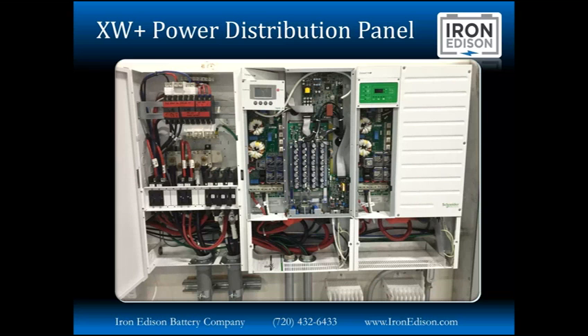What we want to show here is that the conduit extension boxes that run underneath the middle and right inverters have so much room available to do all of the AC and DC wiring. Having worked with 2- and 3-inch conduit, whether it's PVC or metal, it's really tough to squeeze all your wires through the conduit to make these tight bends. It's a really cumbersome process. So these conduit extension boxes, as part of the power distribution panel, provide us so much room to work.